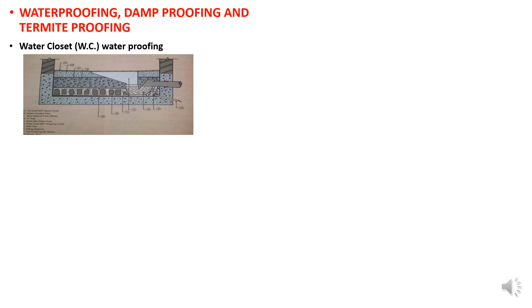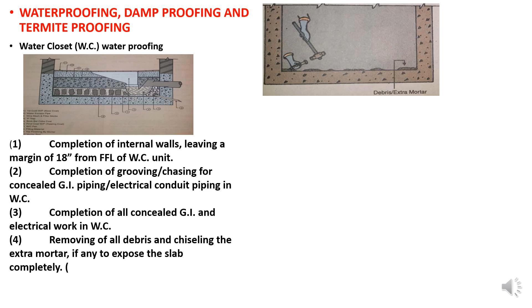Completion of internal walls leaving a margin of 18 inches from FFL for a WC unit. Completion of grooving and chasing for concealed GI piping and electrical conduit piping in WC. Completion of all concealed GI and electrical works in WC. Removing all debris and chiseling the extra mortar, if any, to expose the slabs completely. See here, this is the methodology of removing the extra mortar.